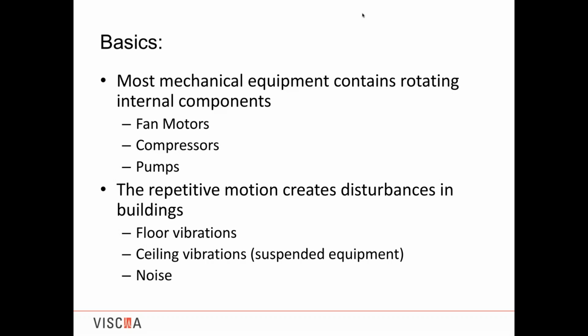Now, sometimes on this equipment, the vibration of the equipment itself can be damaging to the equipment. So you're not only isolating the vibrations from coming into the building, you're isolating the equipment to prevent it from damaging itself. And as you know, most of this equipment, if you're familiar with the industry, compressors especially, the manufacturer will put some kind of little, maybe cheap rubber grommet underneath their compressor to try to prevent some vibrations, but that's not going to solve your problems from coming into the building.